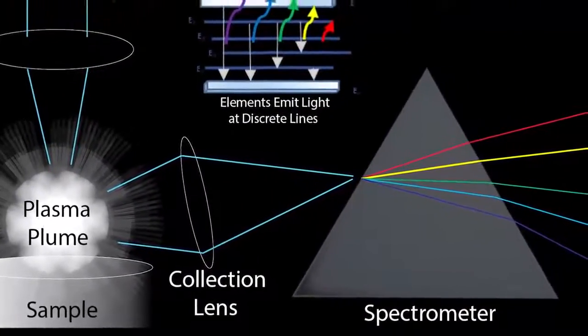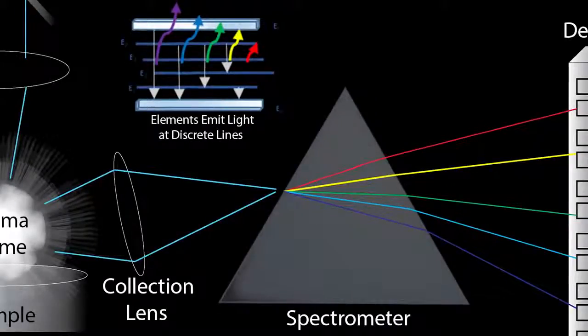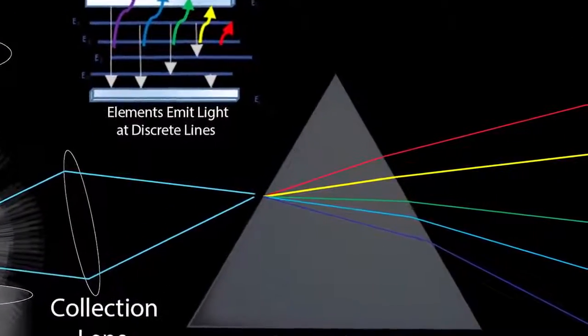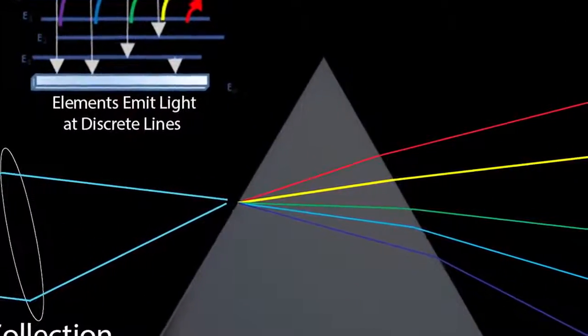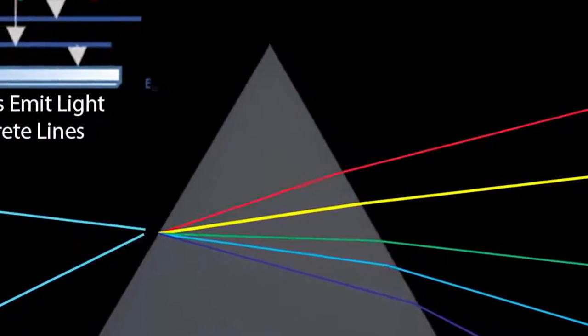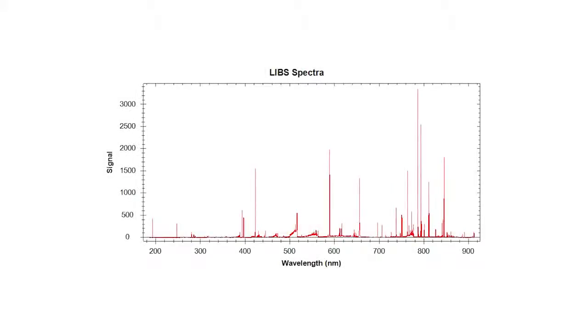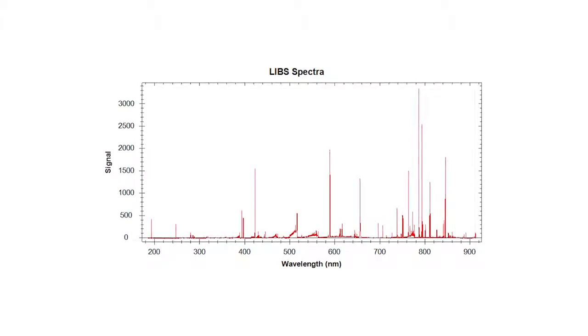As the electrons return to their ground states, light of wavelengths specific to elemental composition is emitted from the plasma and collected by the spectrometer. The spectrometer separates all light emissions with high-resolution optics for the advanced charge-coupled device. The elements detected in the sample can be viewed in a graph of the intensity of the emitted light versus the wavelengths at which they occur.